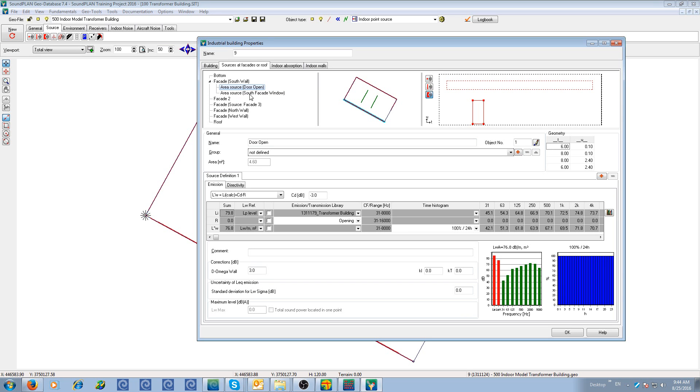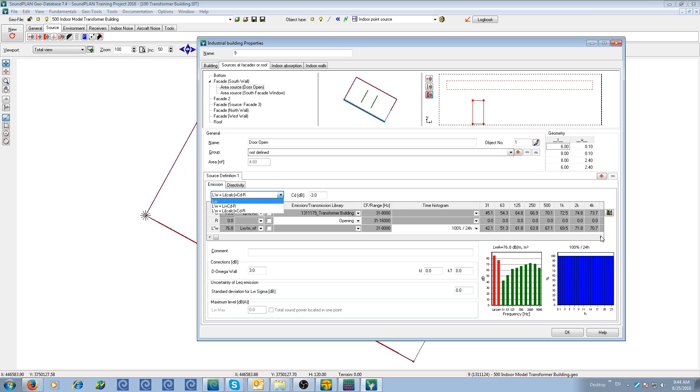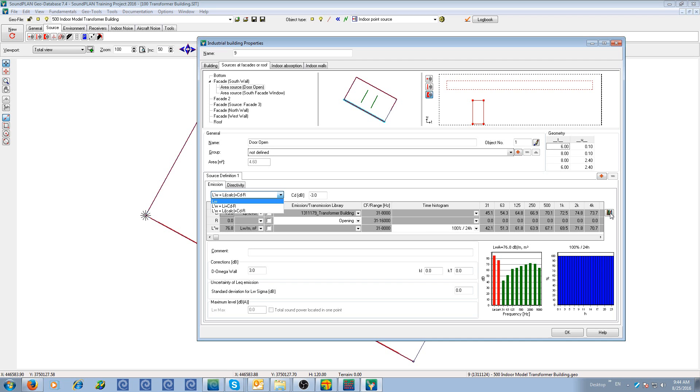Now for each of these area sources, we have different options of characterizing the source. LW stands for just the power level. We would assign a library definition of a sound power level of that source. That could be an intensity level or the sound power for the entire area. So if you have a louver, an acoustic louver that has a fan behind it, you can put in the sound power level of the fan. If you have a point source on the outside of the building, you can put the sound power level of that point source.